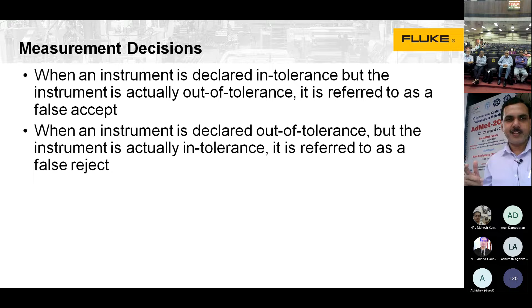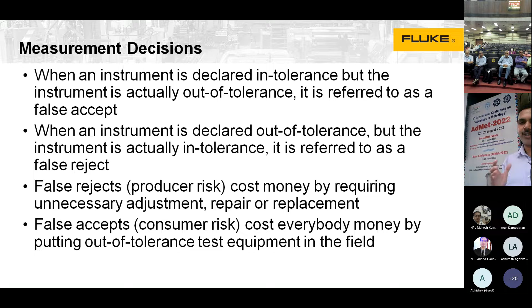Okay. So false reject costs money by requiring unnecessary adjustment, repair, or replacement. Whereas, as I mentioned, false accept is the consumer's risk, because there is a probability that it could be outside the limit. So it costs everybody money by putting out of tolerance test equipment in the field or in the market. The chance of making a false accept or false reject can be understood as a probability, which is usually expressed as a percentage. When a customer requests a calibration, they usually don't worry about false reject risk, but may specify a maximum acceptable false accept risk.